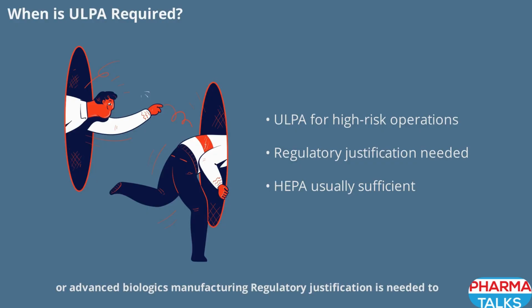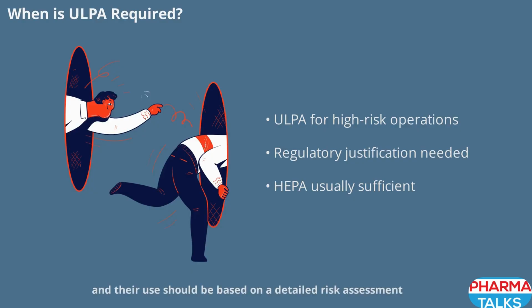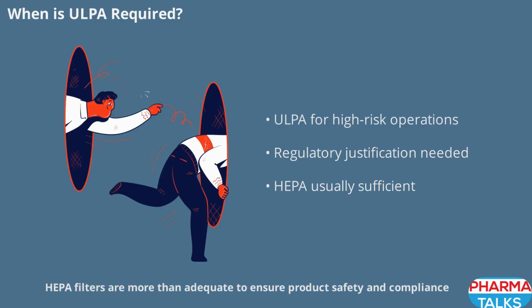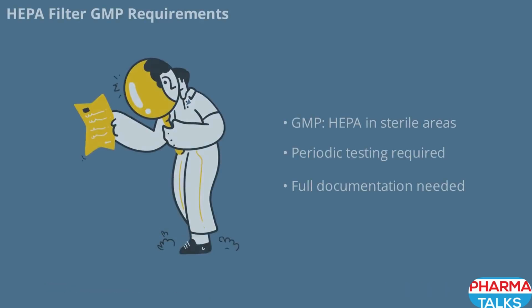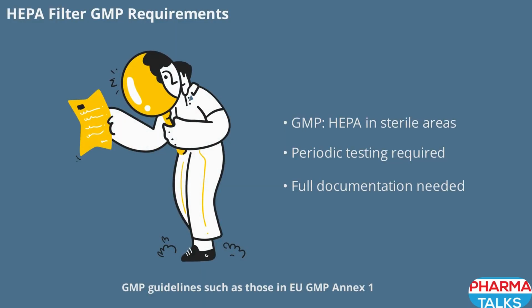Regulatory justification is needed to use ULPA filters in pharmaceutical settings, and their use should be based on a detailed risk assessment. For most pharmaceutical applications, HEPA filters are more than adequate to ensure product safety and compliance. GMP guidelines, such as those in EU GMP Annex 1, require HEPA filters in sterile manufacturing areas, especially in grade A and B environments. These filters must undergo periodic testing to ensure ongoing performance and must be fully documented as part of the facility's quality control system.